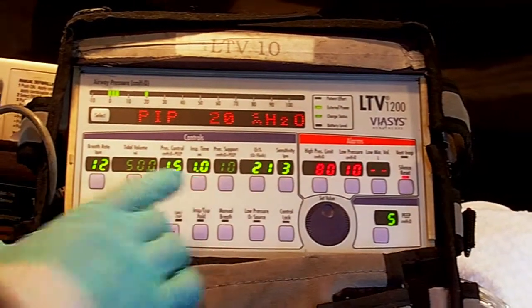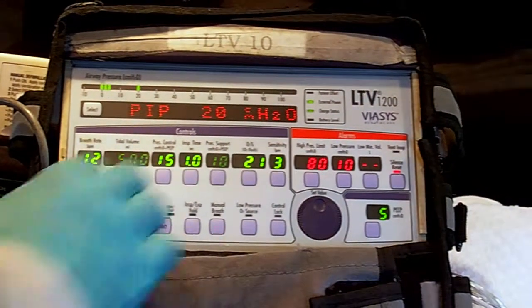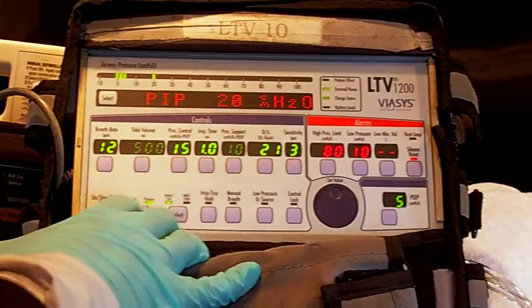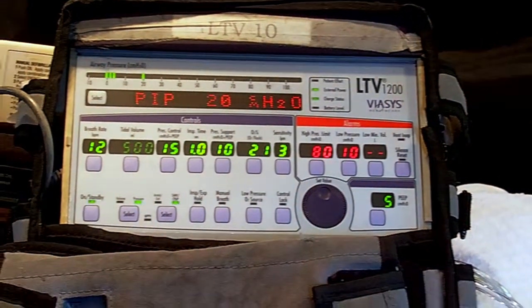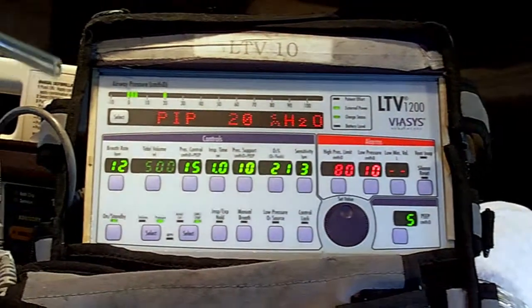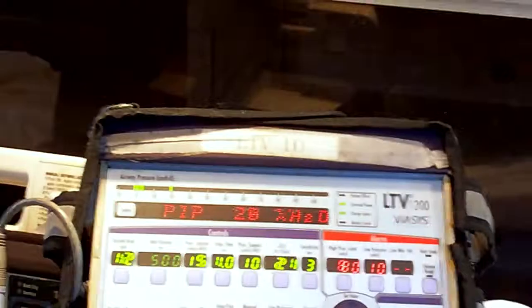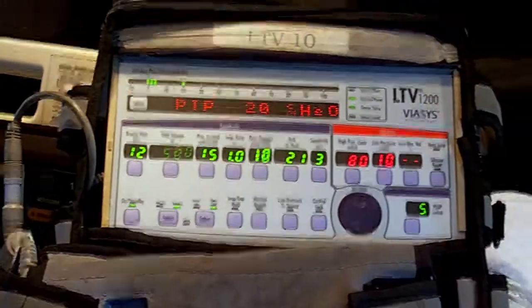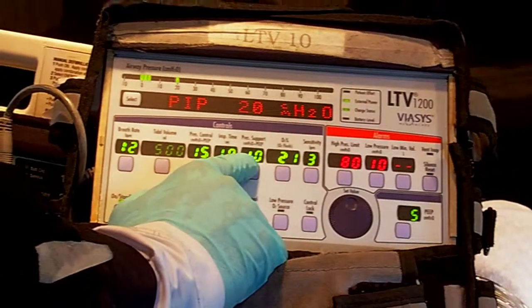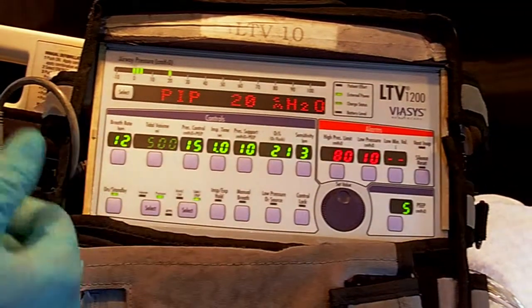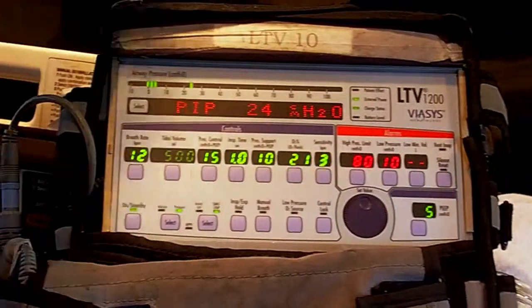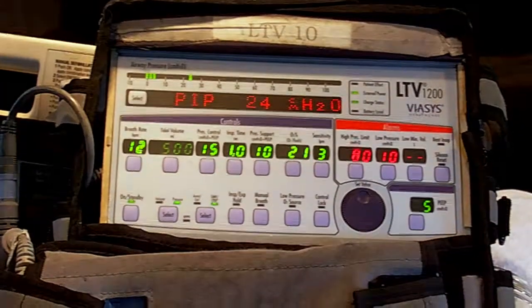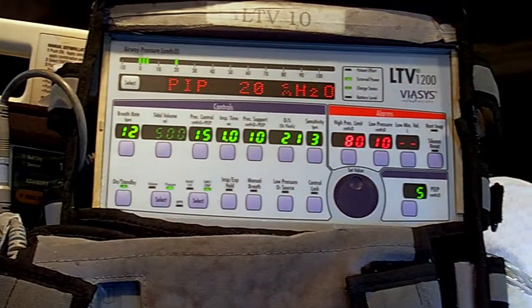Following that, we have pressure support. Pressure support is usually found in modes such as SIMV. In this case, what's going to trigger it is patient effort — the patient is going to suck on the tube to tell the ventilator to trigger. The target is going to be 10 centimeters of water pressure. And what's going to tell the ventilator to cycle off is a reduction in the circuit — dropping the circuit pressure tells the ventilator to stop gas flow and go into exhalation. So those were the five basic breath types.